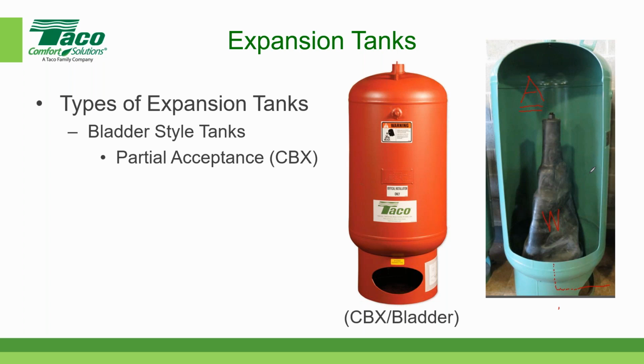So we're talking about normal operation. Under normal operation, the water is physically separated from the air by the rubber membrane in the bladder, so it doesn't go into solution. So it makes it much easier to control the air that's in your system. Air is not a good thing in a piped hydronic system. And as the second thing, as I said, it also allows for a physically smaller tank because you can pre-charge or pressurize the tank before you connect it to the system. So those are the two major reasons. Great. I mean, keeping the air and water separate and the size of the tank, that's the simple answer.